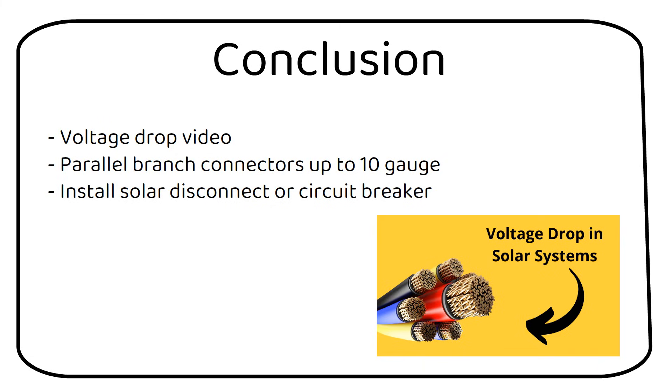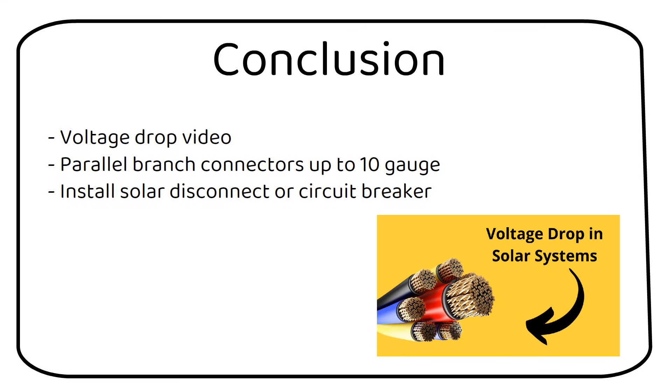You need to install a solar disconnect switch between the solar panels and the charge controller. This can be a solar disconnect switch or a circuit breaker. If you choose a circuit breaker, it's best to place it near your charge controller. Then you don't need a separate combiner box. Make sure the voltage is high enough for the solar panel voltage. A battery disconnect switch is not suited because it's high current, low voltage.